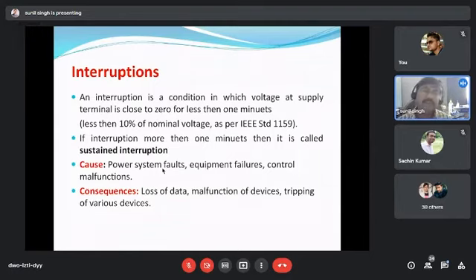For short-term interruptions, if a fault occurs and it is a self-clearing fault, like lightning, then it may take less than 1 minute. So an auto-close circuit breaker may clear these types of short interruptions, so the supply is automatically restored.